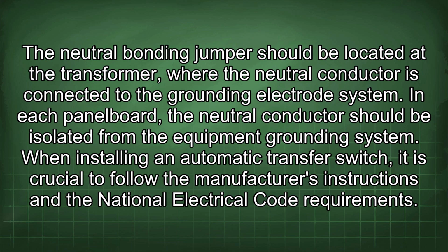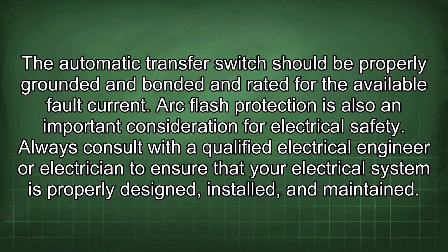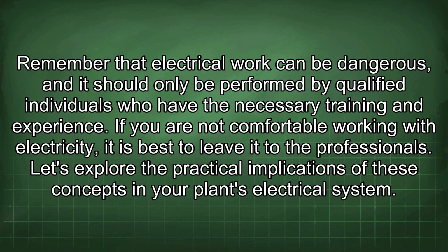When installing an automatic transfer switch, it is crucial to follow the manufacturer's instructions and the National Electrical Code requirements. The automatic transfer switch should be properly grounded and bonded and rated for the available fault current. Arc flash protection is also an important consideration for electrical safety. Always consult with a qualified electrical engineer or electrician to ensure that your electrical system is properly designed, installed, and maintained. Remember that electrical work can be dangerous, and it should only be performed by qualified individuals who have the necessary training and experience. If you are not comfortable working with electricity, it is best to leave it to the professionals. Let's explore the practical implications of these concepts in your plant's electrical system.